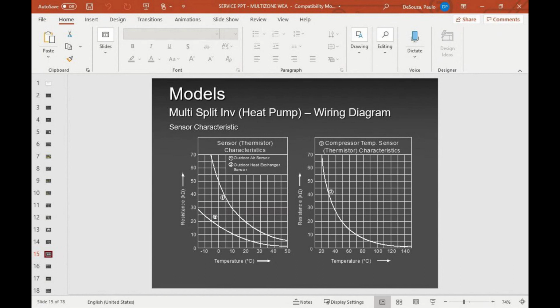So this is your explanation, guys. What's highlighted over there is the sensor, and on the top here is your electronic expansion valve. Every sensor will tell the electronic expansion valve if I need more juice or less juice, more refrigerant or less refrigerant. Over there, that's your compressor. On top of the compressor is your high pressure discharge temperature sensor. Obviously, you won't be able to see much over here, but that's the wiring. And that same wiring you will see on the top cover. When you open up the top cover on each and every unit, you will see this wiring diagram, whether it's a 2-zone, 3-zone, 4 or 5-zone.